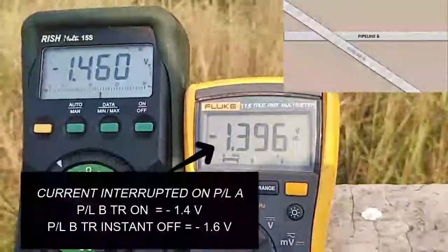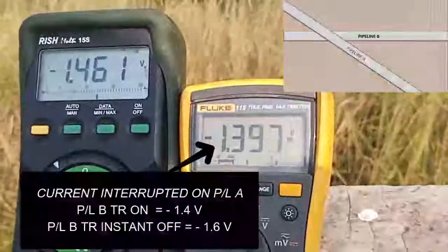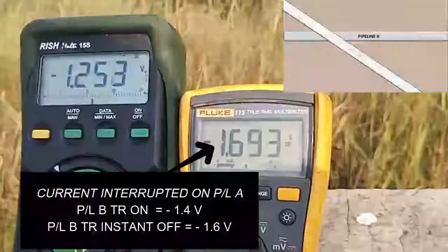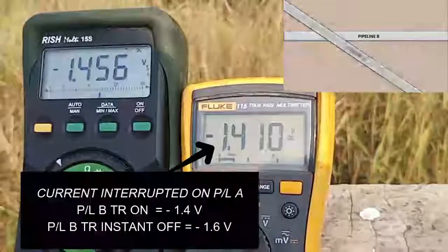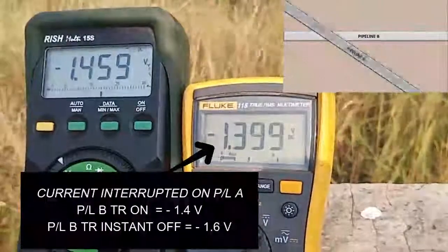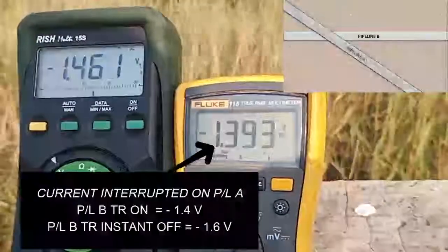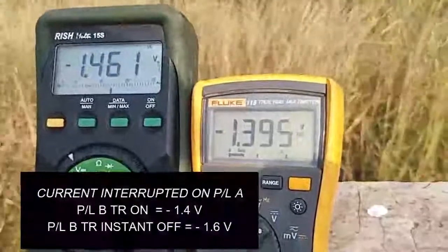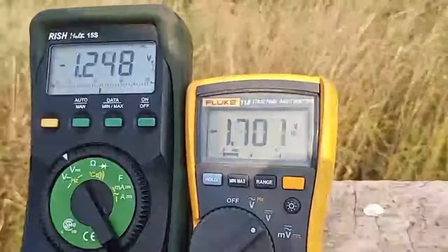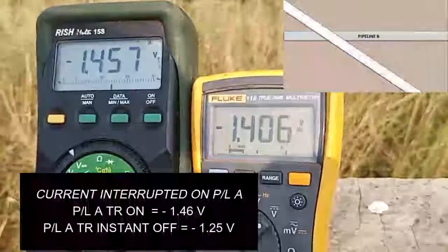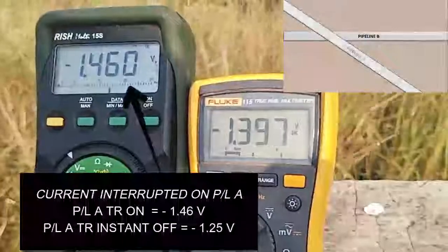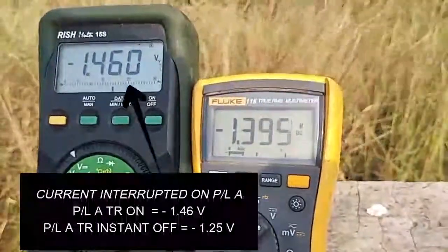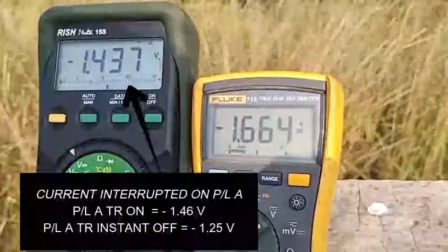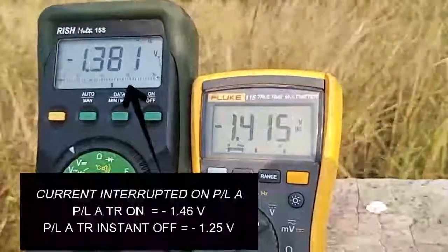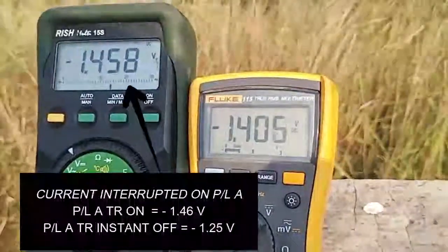The on potential of Pipeline B is minus 1.4 volts and the instant off potential of Pipeline B is minus 1.6 volts. On the contrary, the on potential at Pipeline A is minus 1.46 volts and the instant off potential of Pipeline A is minus 1.25 volts.